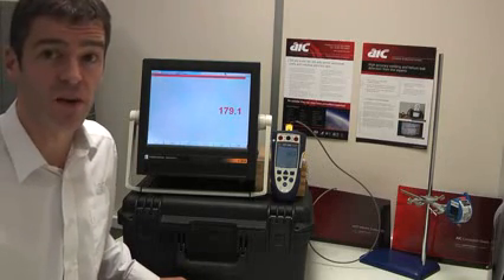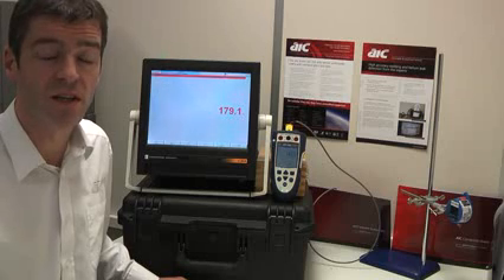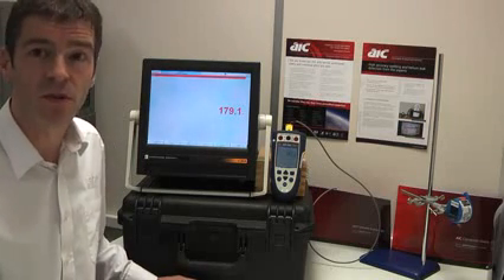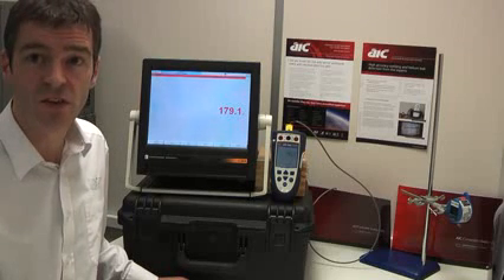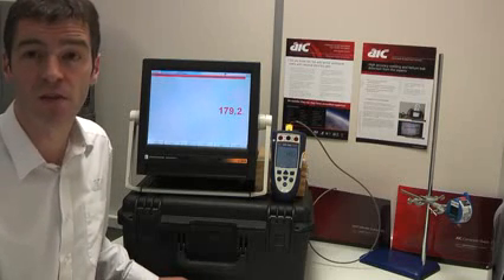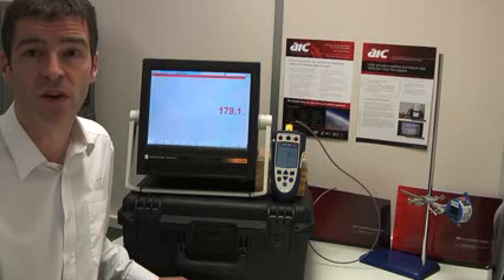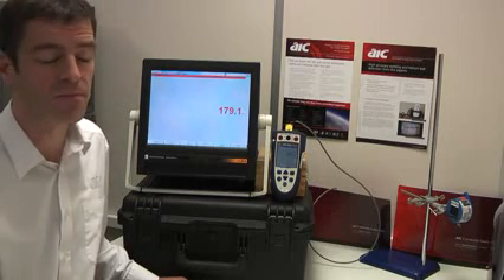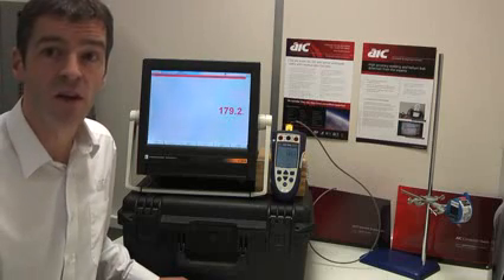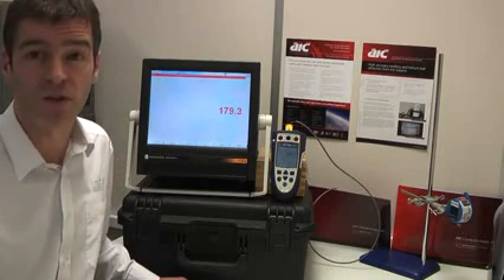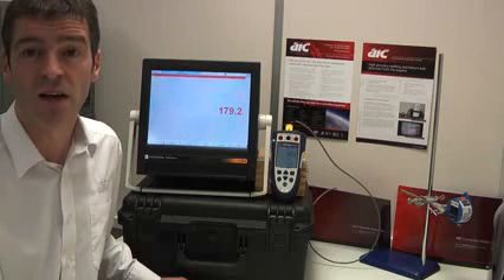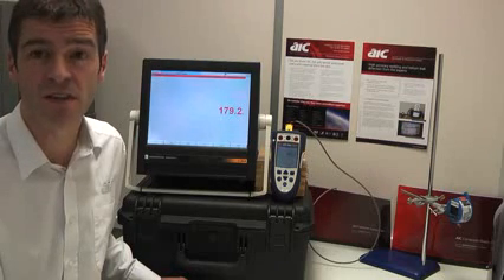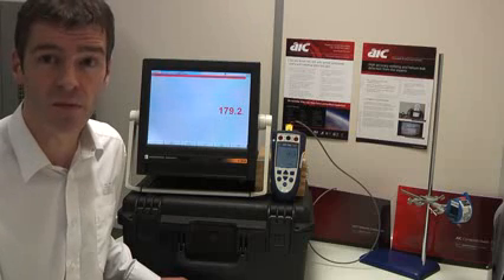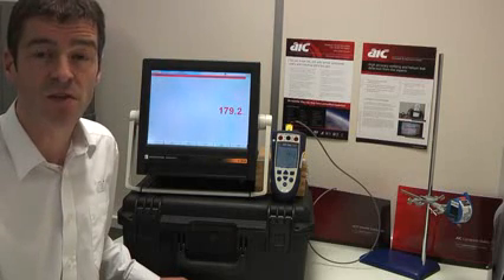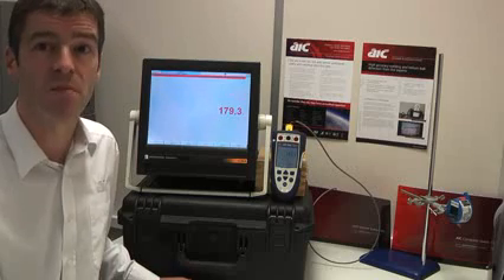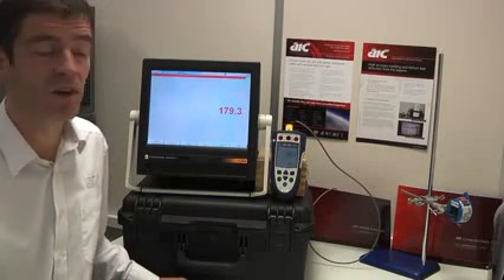Of course, it's very unlikely in practice that you'd have the wrong type of cable installed in the machine. What's more likely to happen is that the cable that's permanently installed in the machine ages and drifts from contamination and normal thermal cycling, which affects all base metal thermocouples to one degree or another. And over a period of time, you diligently calibrate the autoclave by plugging into the sockets and measuring it at the instruments, and every time you do it, you get the right answer. But when you actually heat the machine up and operate it, there is now a temperature gradient in that part of the cable, and it becomes a significant source of error.